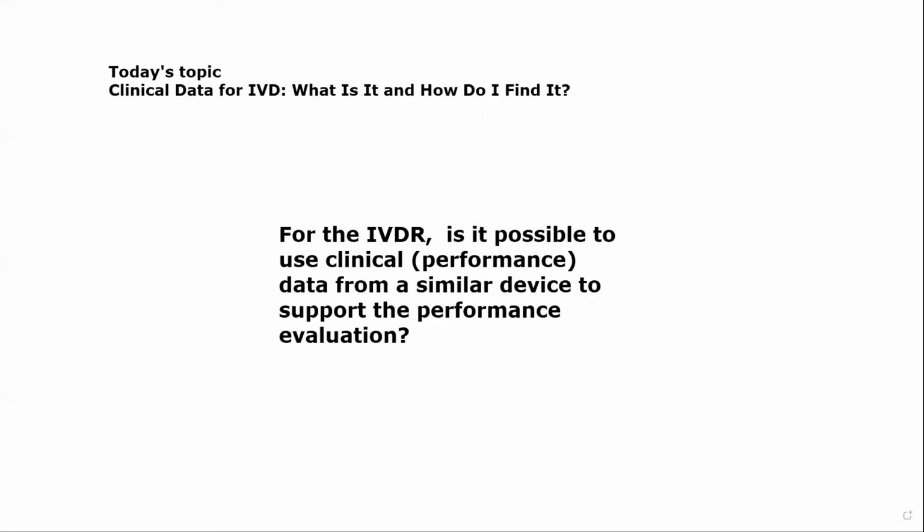This is Laurie. I'll just jump in there saying, Sarah, that answer was perfect. And I'll summarize one last time for emphasis: in the performance evaluation report of the subject device, the goal of that PER is, as I always say in our webinars and to anyone who will listen, the PER ultimately has one job to do, and that is to, at the end of it all, establish the safety and performance of the device under evaluation, the subject device, as it relates to IVDR.